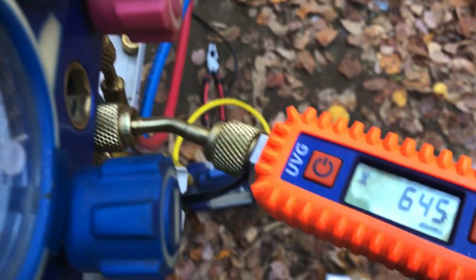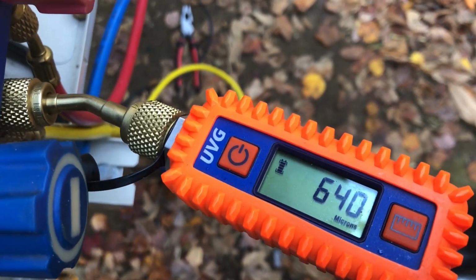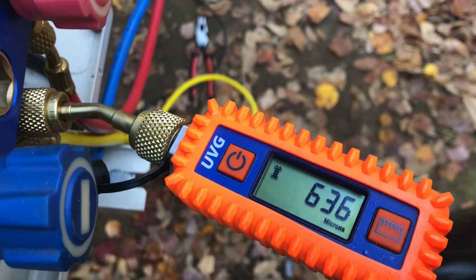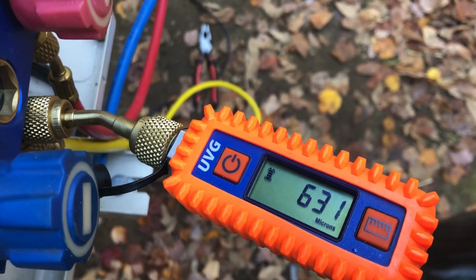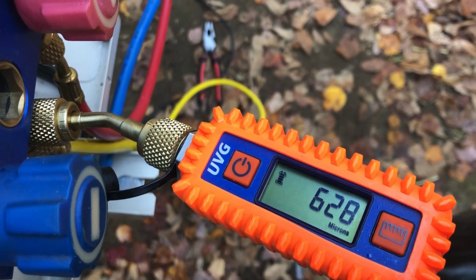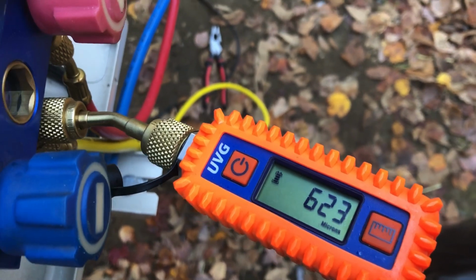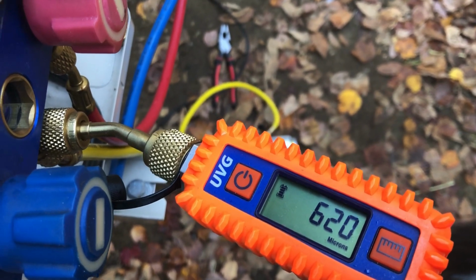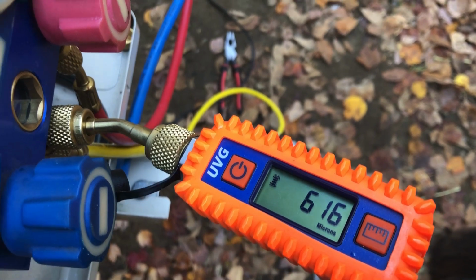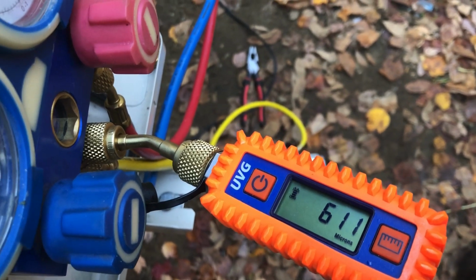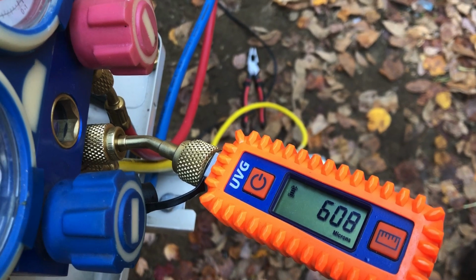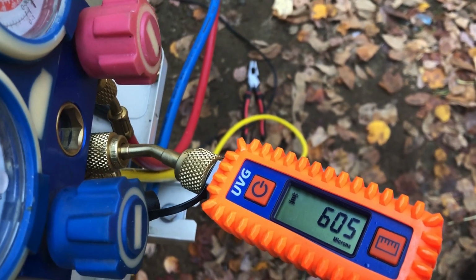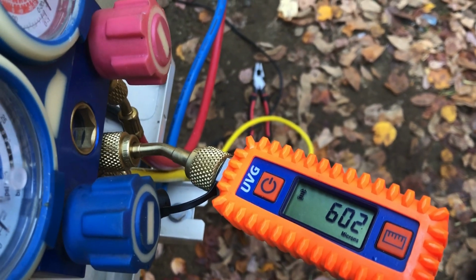I have a micron gauge. The micron gauge is sensing the amount of moisture in the line. I want this to drop below 500. This thing has only been running for about 30 seconds and it's already dropping extremely fast. The reason why this is dropping so fast is because I just used nitrogen in the lines, and nitrogen dries out the lines extremely quick, so it makes the vacuuming process much simpler.